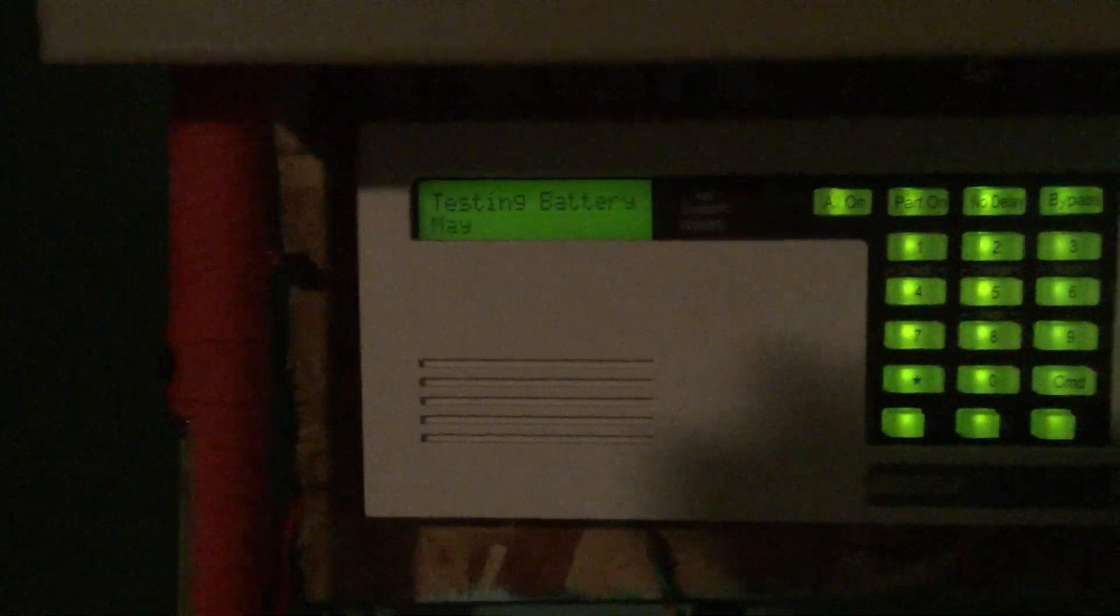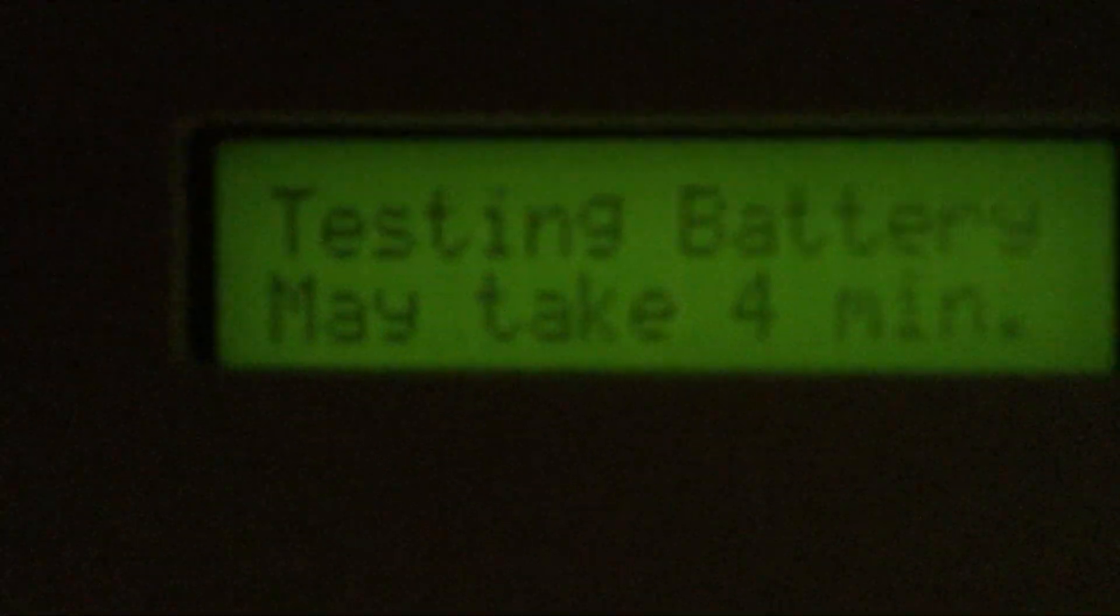So that is basic functions. And let's do some other things. Let's show a bell test. So for a bell test we do, I believe it's command 41. Let's try it, command 41 and enter our code. Okay, and then it tests the battery afterwards. You can actually set what it tests. We're not going to wait four minutes. We're just going to press command and now we're back to normal.